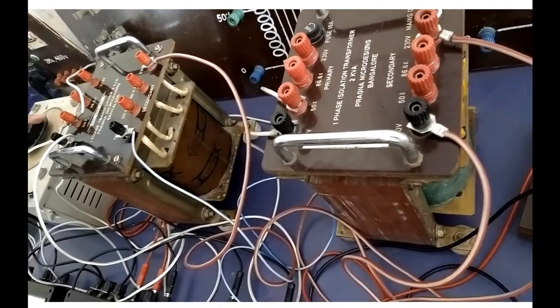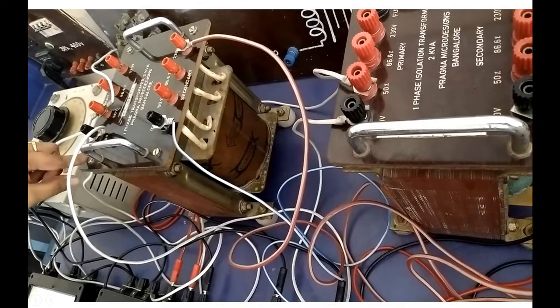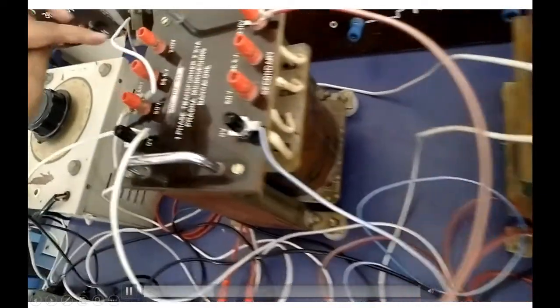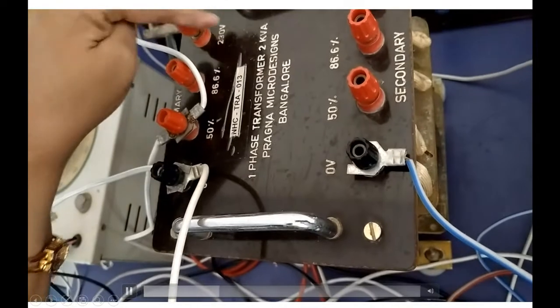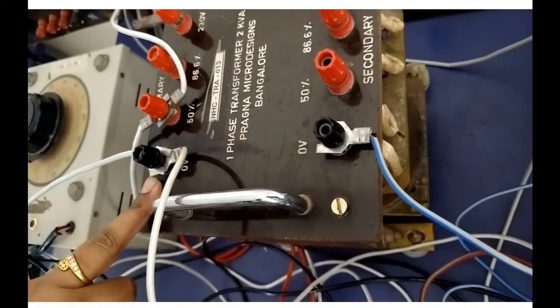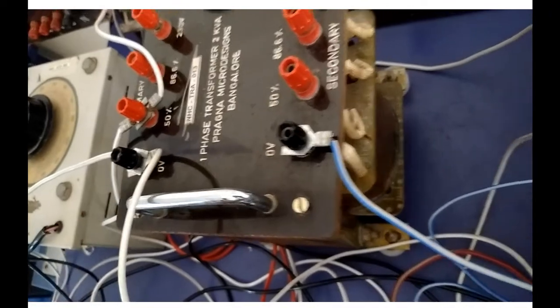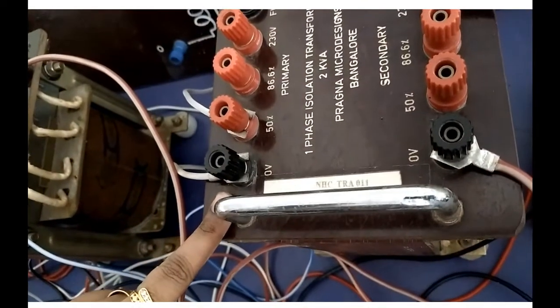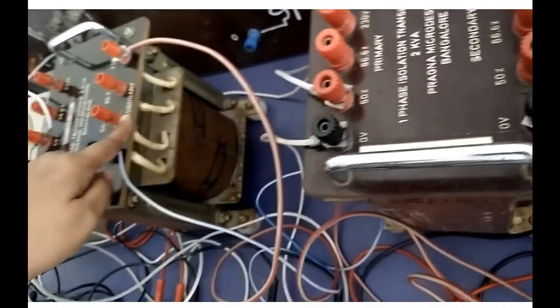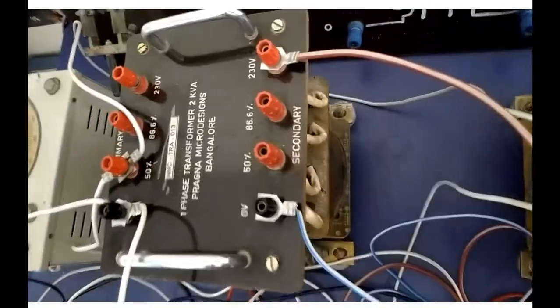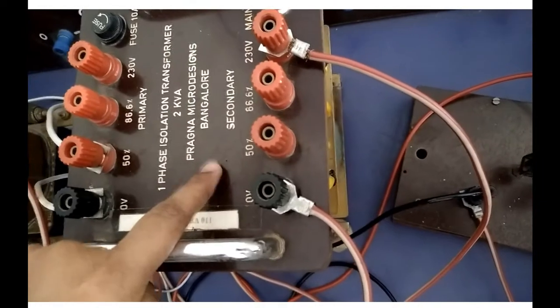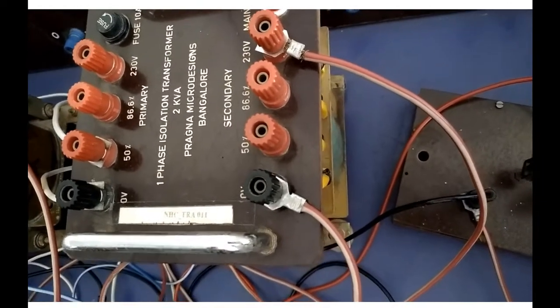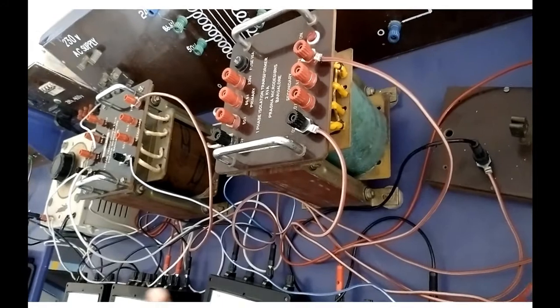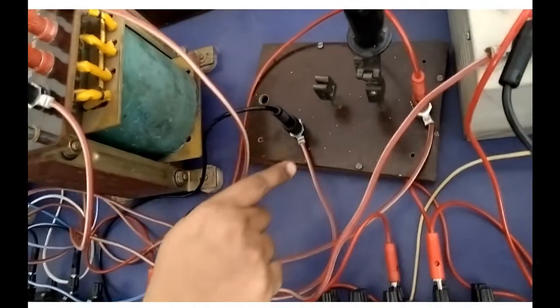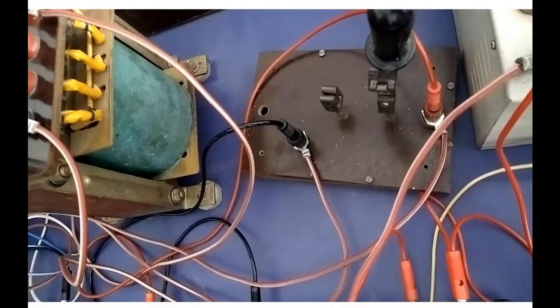Okay, so see the first transformer, the primary voltage we are going to take is 115, that means 50% of 230. So the primary voltage I am going to consider here is 115 volt. Here also the primary we are going to take 115 volt. Secondary you can see 230 volt, and the second transformer also we are going to take 230 volt. And the precaution here is that you can see the SPST switch is open. So now we will perform Sumpner's test.